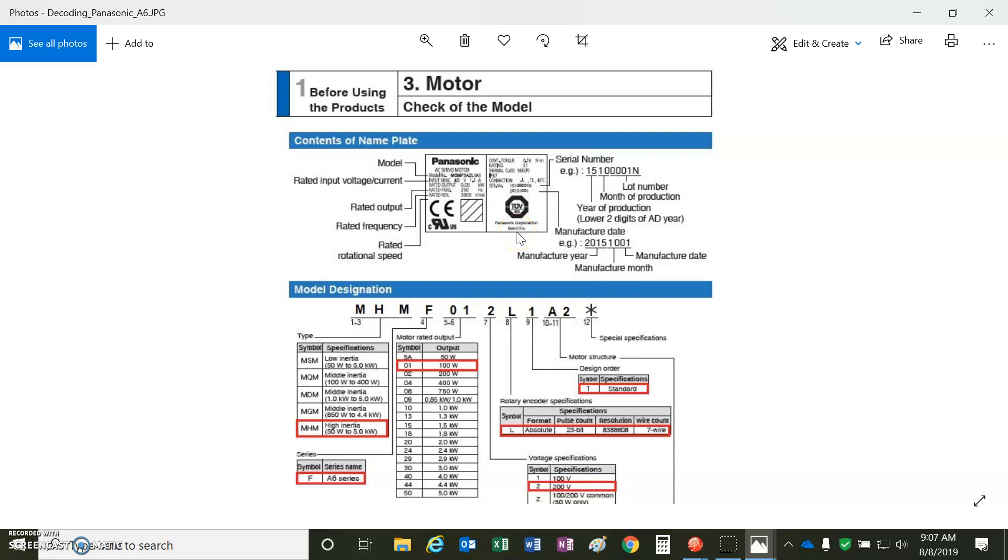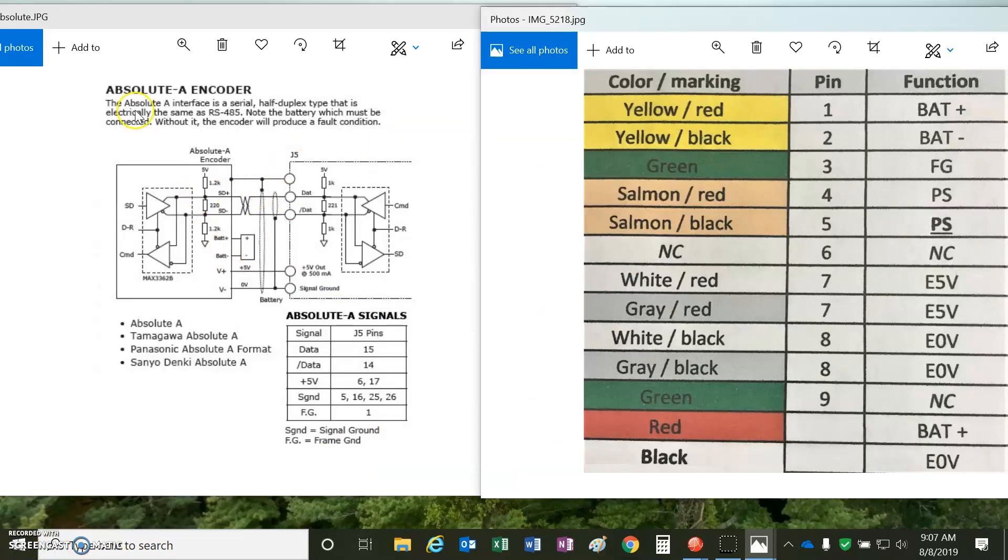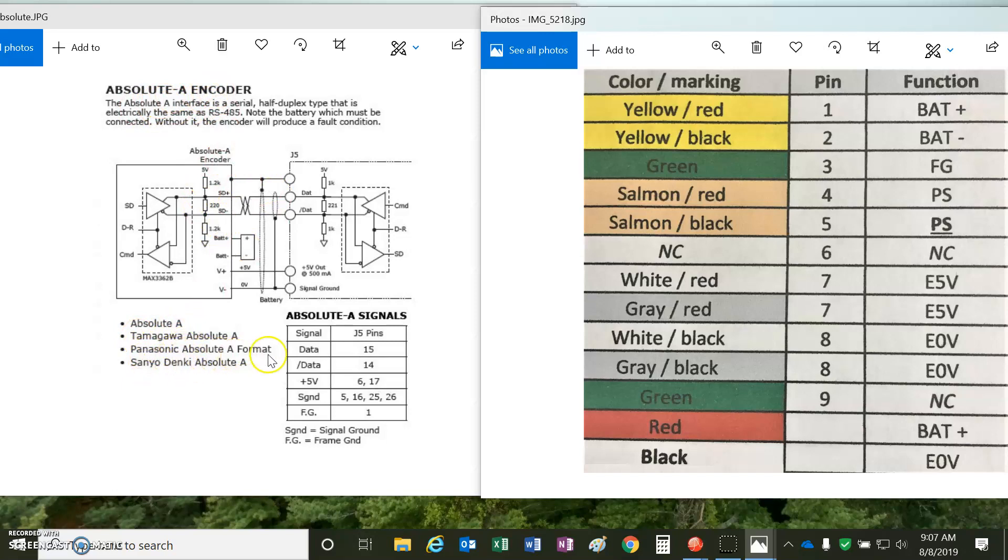I'll talk about that in a minute. But after the wiring, we're going to talk about how to handle 23-bits. So, for the Copley drives, we show how to connect to the Absolute A encoders, and there's various Japanese manufacturers that use the Absolute A, and Panasonic is one of them. The A5 is a 17-bit. The A6 is a 23-bit. That's really the only difference that I saw, except for maybe the motor's a little shorter stack, which is cool.